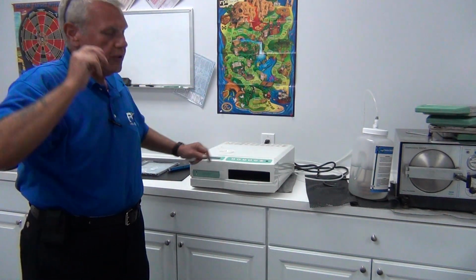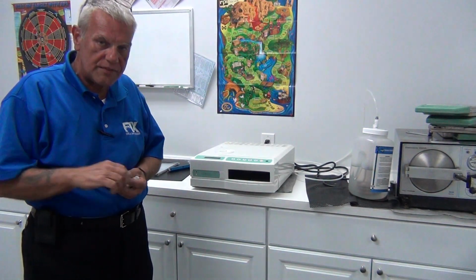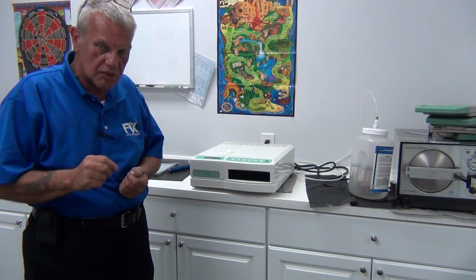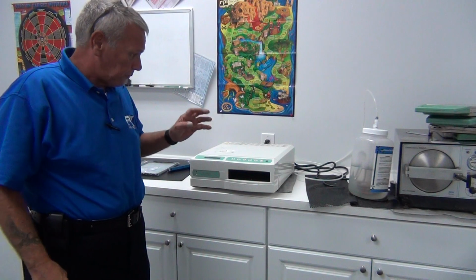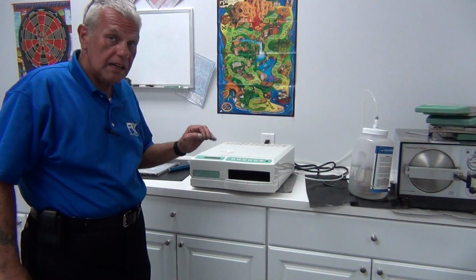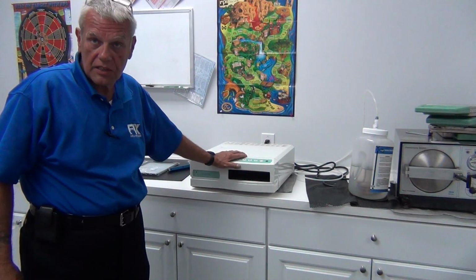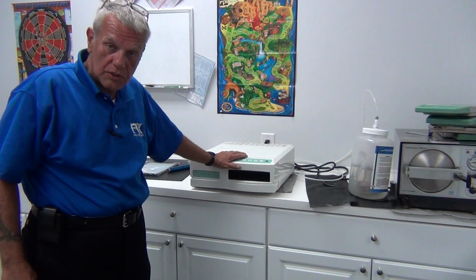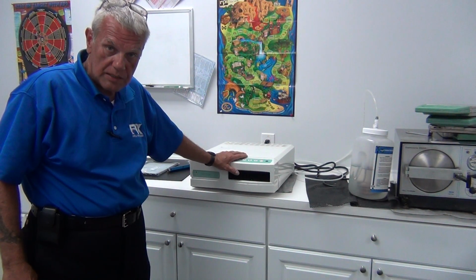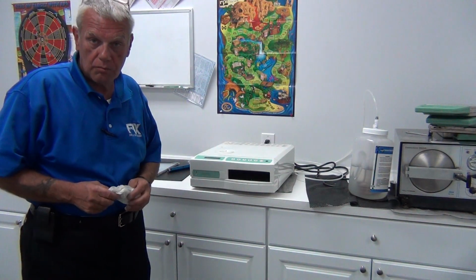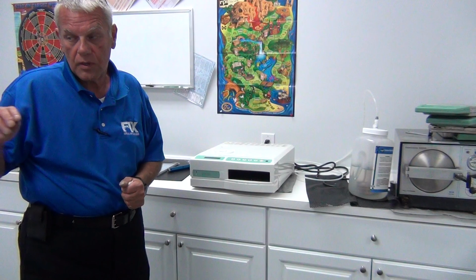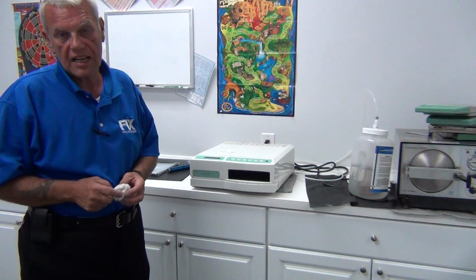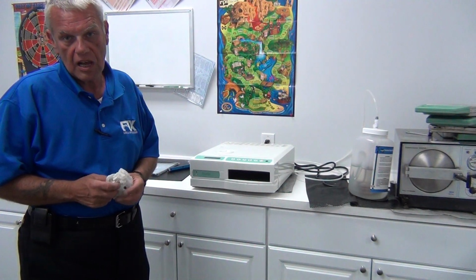You may even, while you're doing your sterilizer maintenance, the sterilizer is usually next to the sink where they receive dirty instruments to hand scrub instruments in the sink. Ladies and gentlemen, hand scrubbing and ultrasonicking is very important with the sterilizer. You've seen the solenoid, that's the only thing that holds the steam pressure in. One piece of debris can get in that solenoid and abort that cycle. That's why it's very important that gross debris be removed from the handpieces before putting into the Statim. It will greatly increase its life.